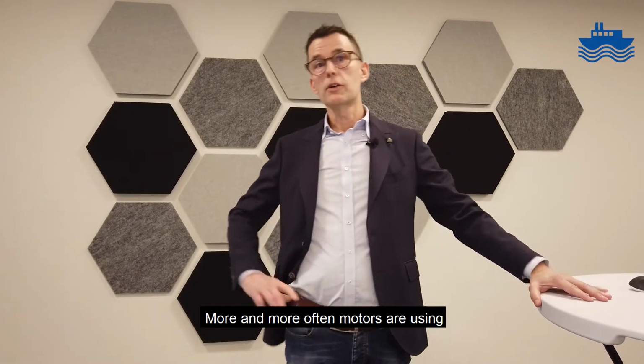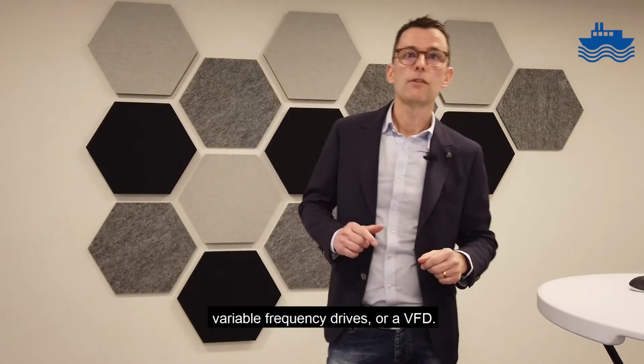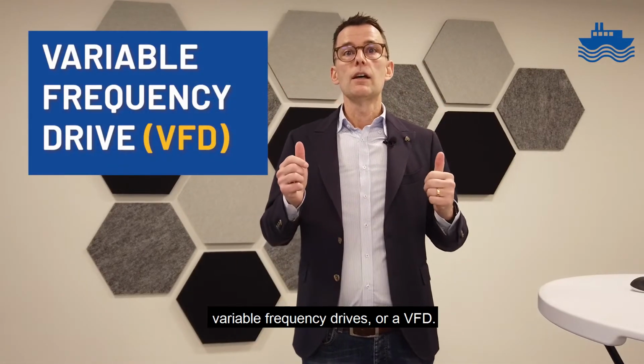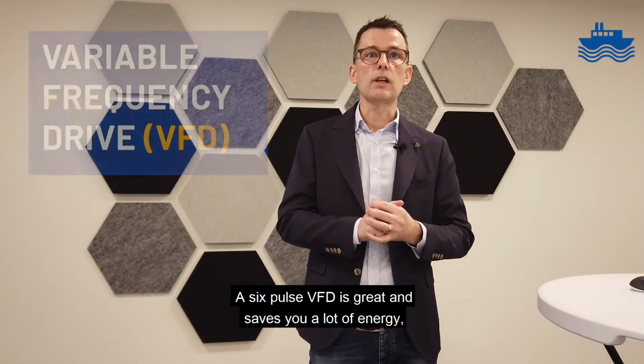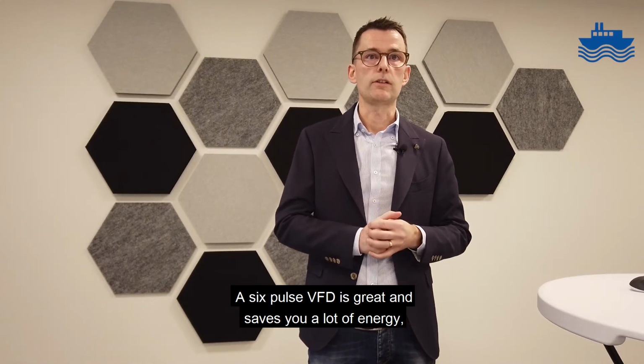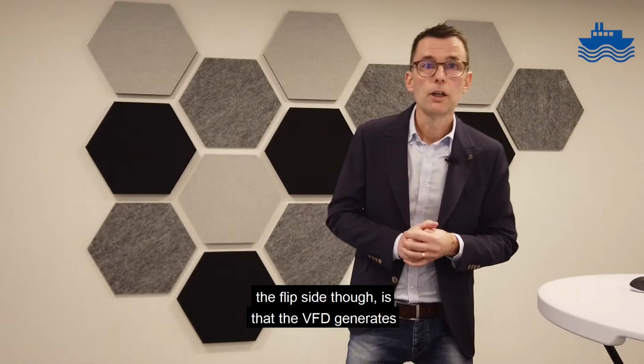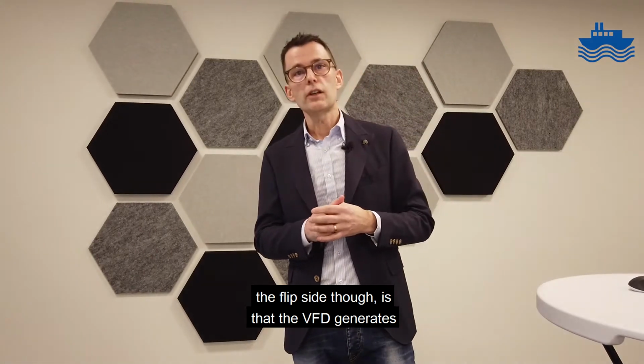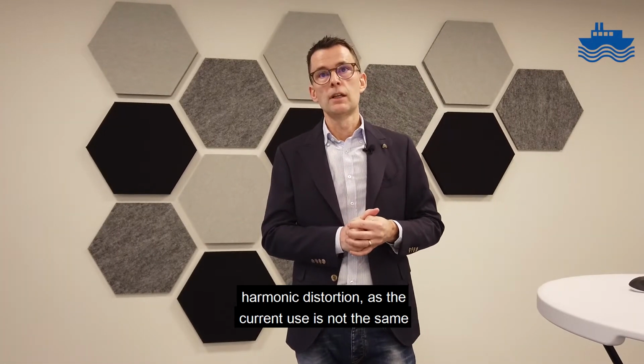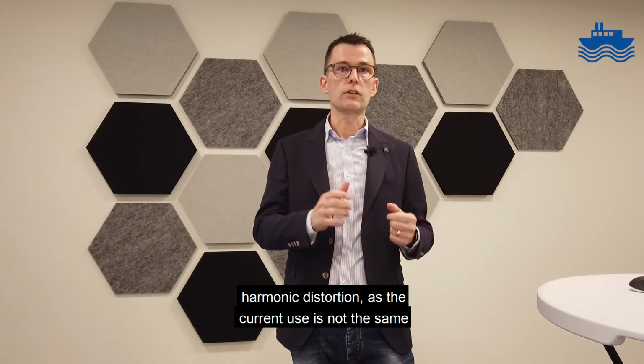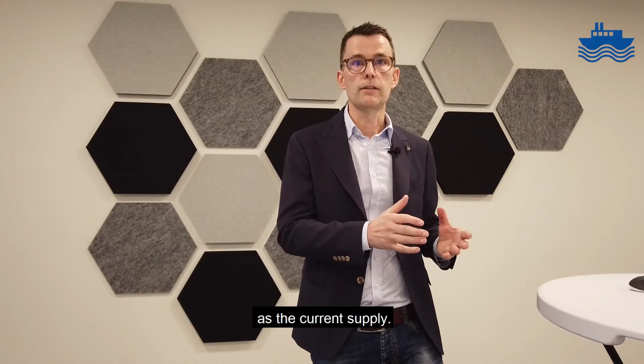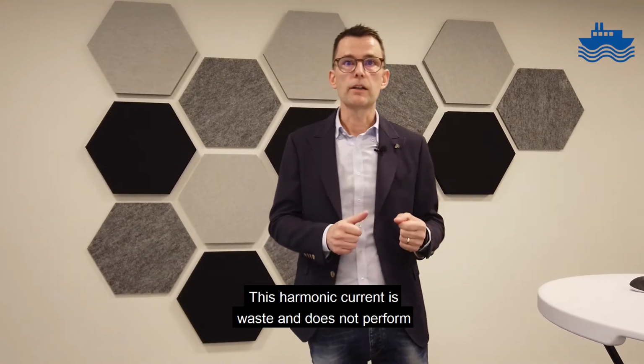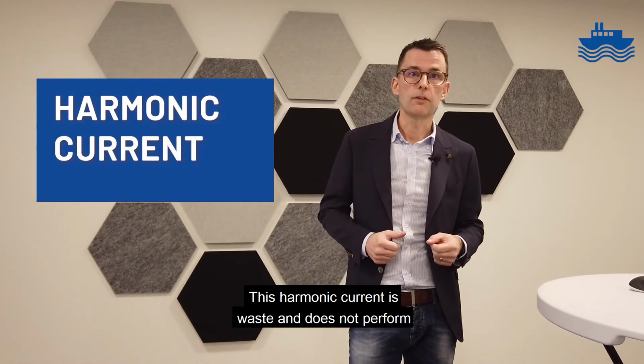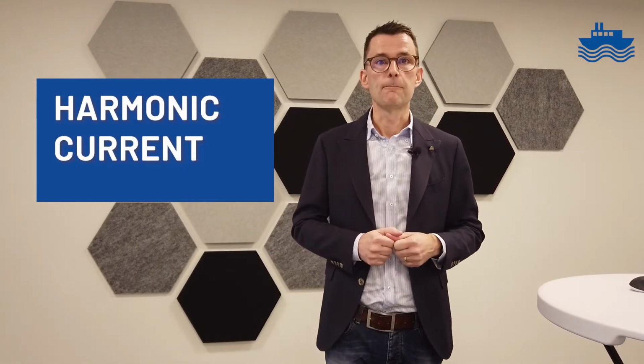More and more often motors are using variable frequency drives, or VFDs. A 6-pulse VFD is great and saves you a lot of energy. The flip side, though, is that the VFD generates harmonic distortion, as the current used is not the same as the current supplied.